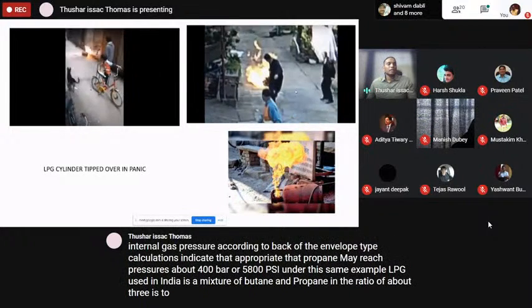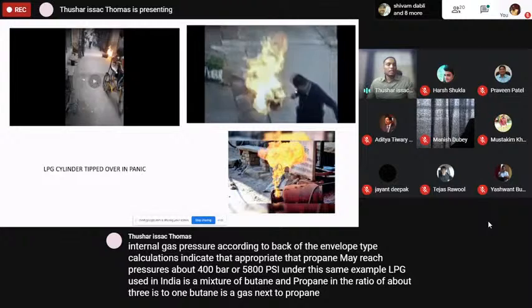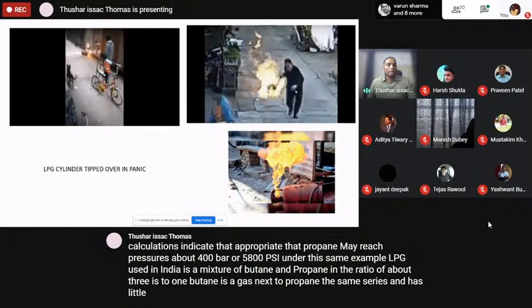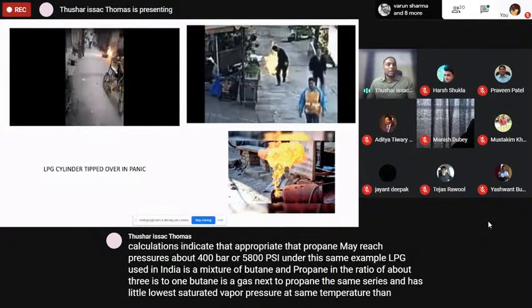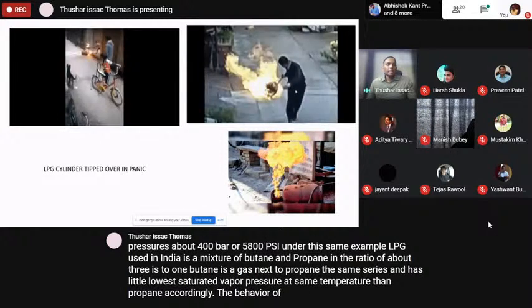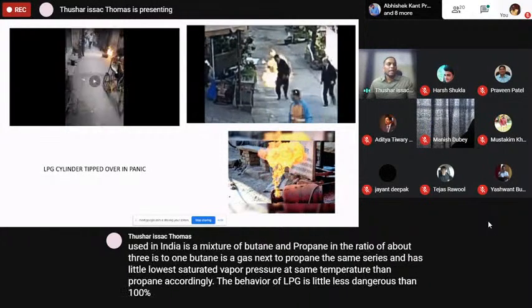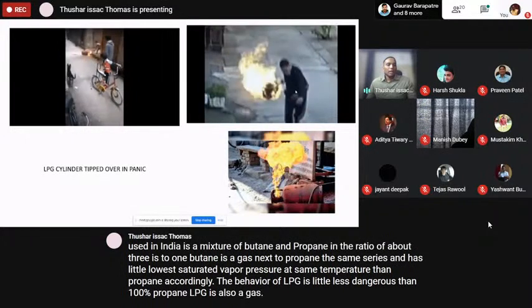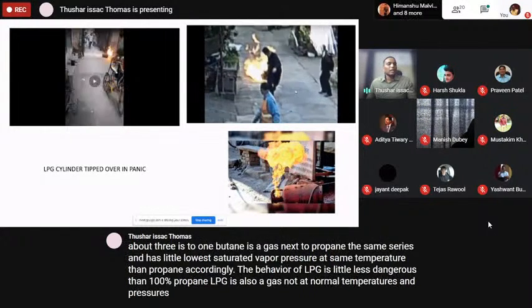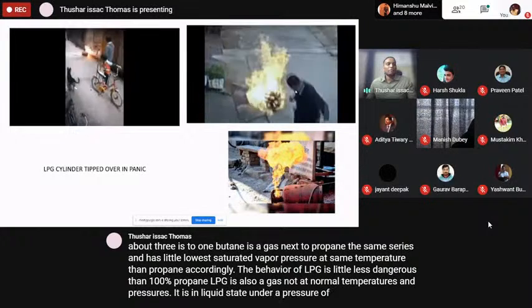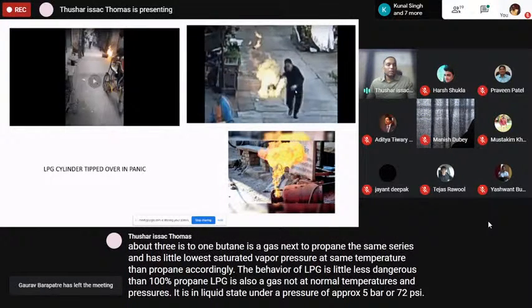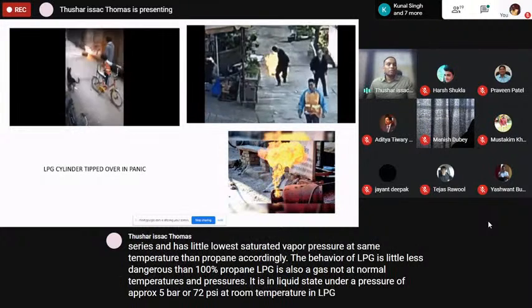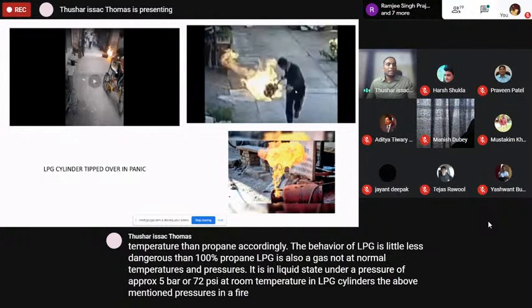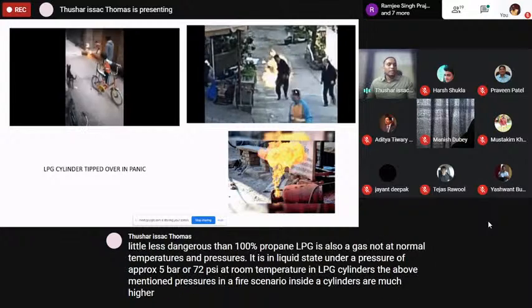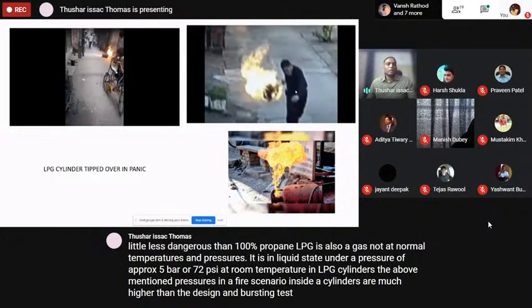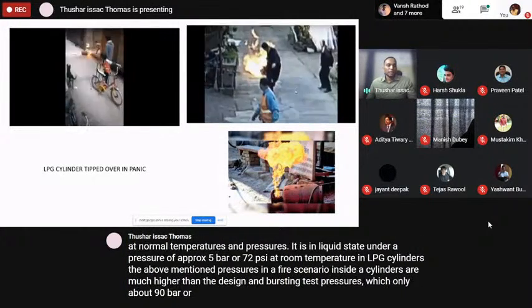3 to 1. Butane is a gas next to propane in the same series and has a little lower saturated vapor pressure at the same temperature than propane. Accordingly, the behavior of LPG is a little less dangerous than 100% propane. LPG is also a gas at normal temperatures and pressures. It is in liquid state under a pressure of approx 5 bar or 72 psi at room temperature in LPG cylinders. The above mentioned pressures in a fire scenario inside the cylinders are much higher than the design and bursting test pressures, which is only about 90 bar or 1305 psi.